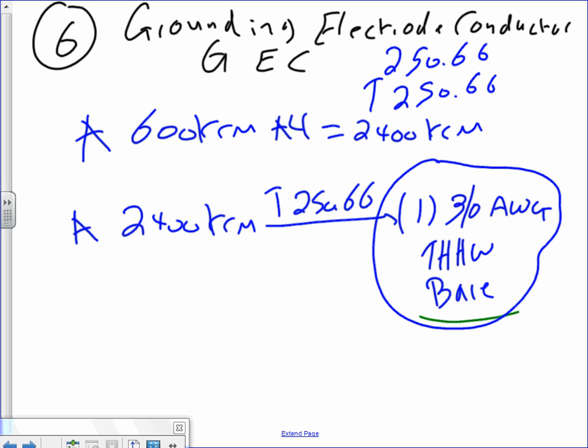Everybody use 250.66. So the only reason they created that table is for like main bonding jumpers and stuff? For the 4 things that we talked about. In the past, guys, before 2014, this table used to be for everything. For the 4 things that I told you about, the neutral and the main bonding and the system and the supply, as well as the grounding electrode. Yeah. Apprentices used to get confused. So they split them. Rightfully so. They put 2 tables. They're almost identical though. All right, grounding electrode conductor.